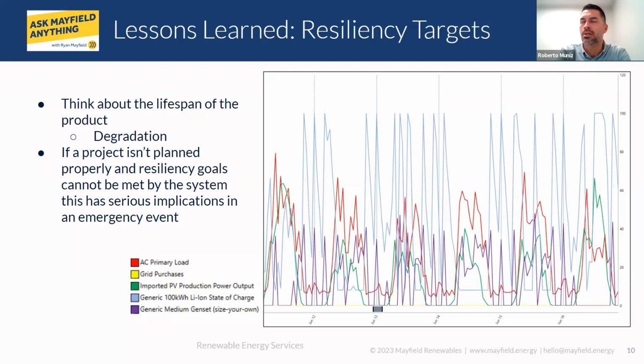On the other hand, we also had systems meant for peak shaving that weren't receiving the commands to do so at the right time, leaving the batteries sitting without any power cycling. It's good for state of charge and state of health for the batteries to keep moving through charge and discharge, not sit idle for a long period. It's very important to understand the application and use the batteries the correct way.